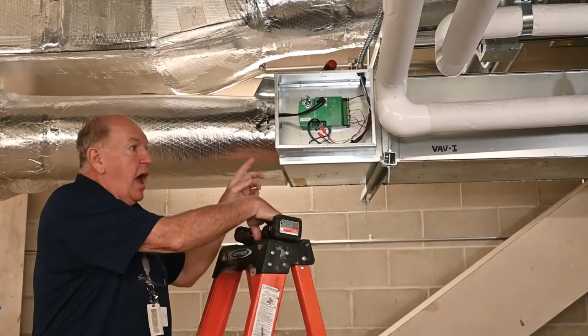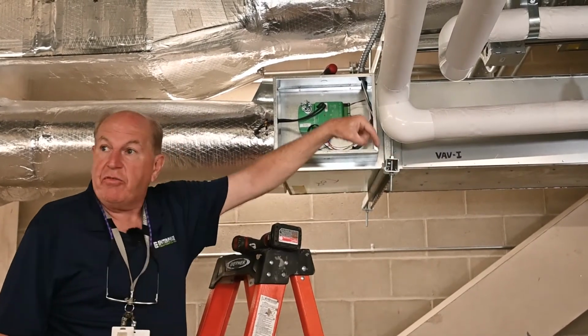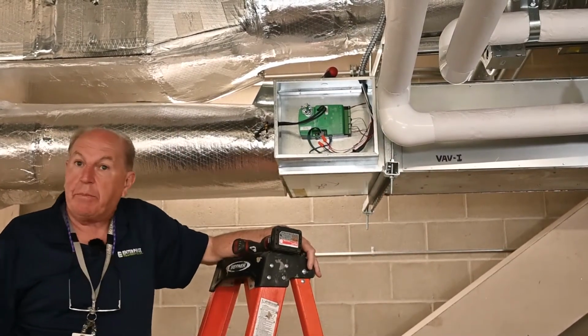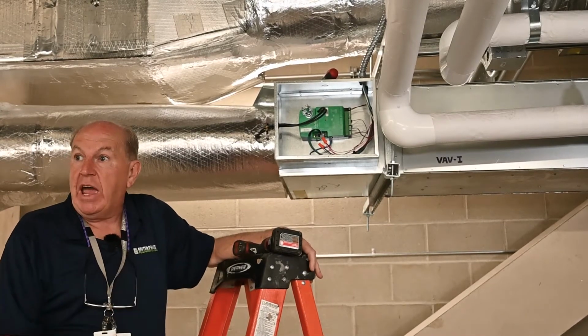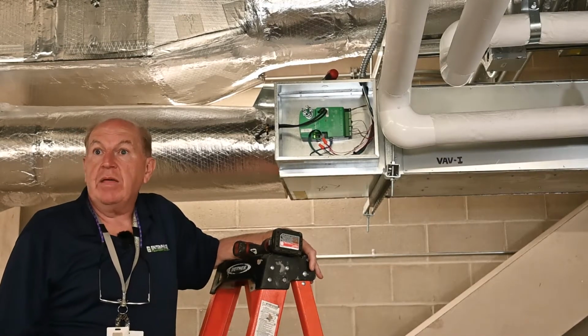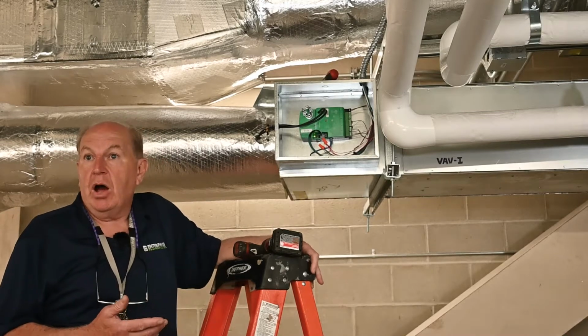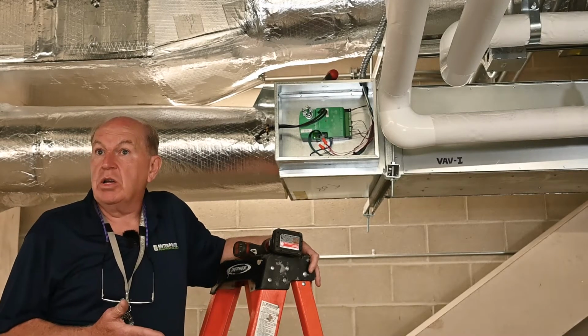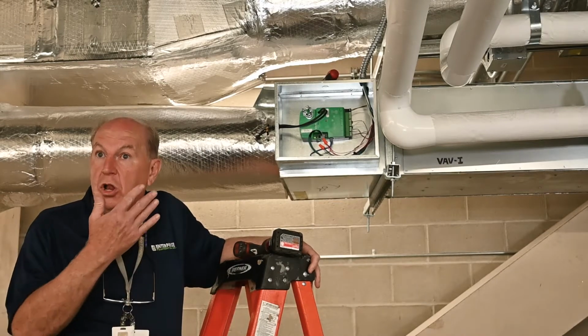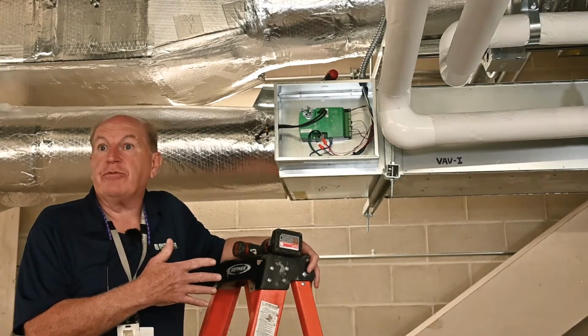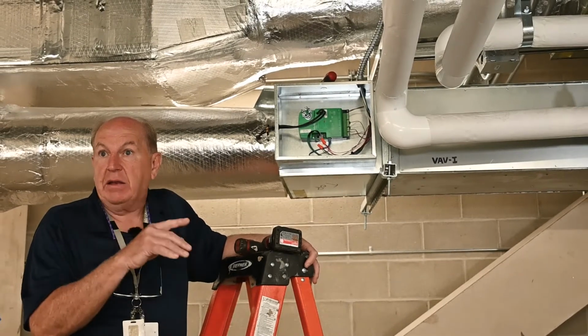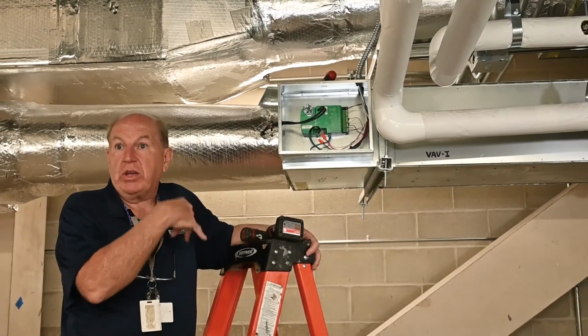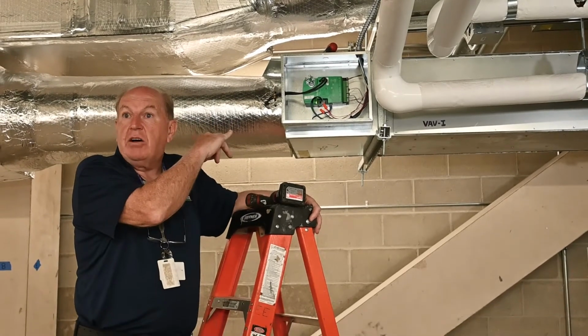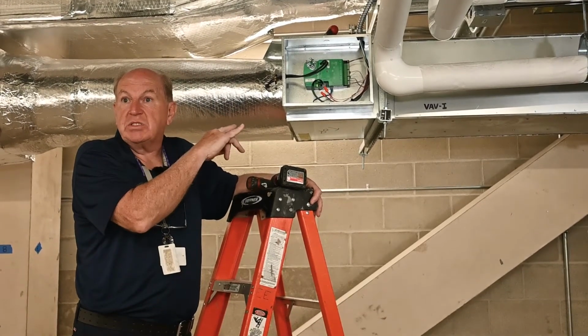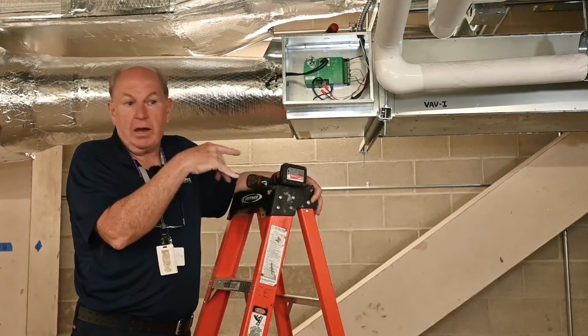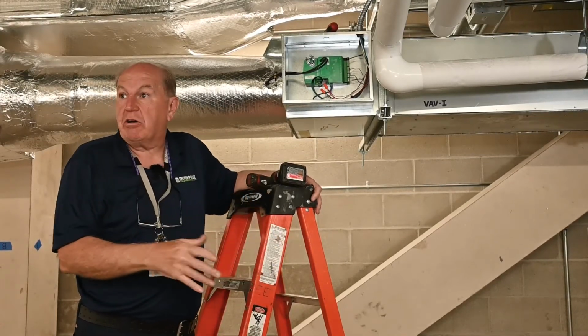Now, one other thing that will happen is over on this duct, every floor it goes through a fire smoke damper. If they shut, you'll get no air in your space. They're tied into a smoky vac panel too. So the fire alarm will close the fire smoke damper, and after the fire's out, they have a button they can press on the 4th floor. It'll do smoky vac, and certain dampers will open, and certain ones will stay closed. There's a list in the drawings of which ones are on smoky vac.